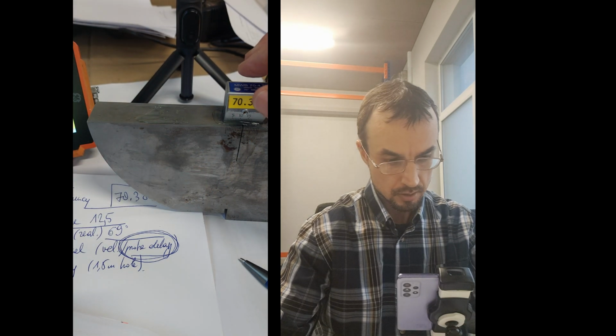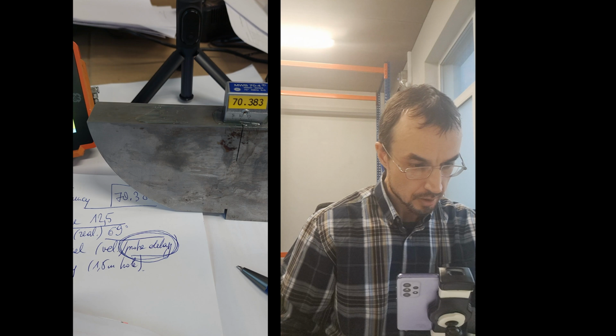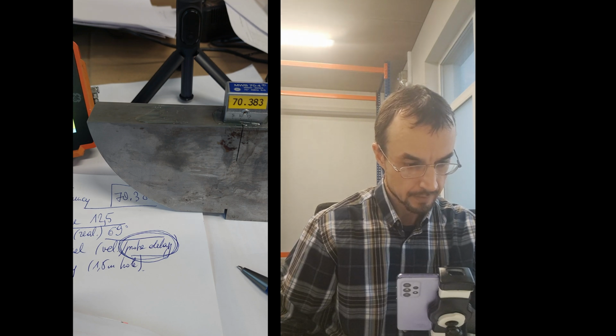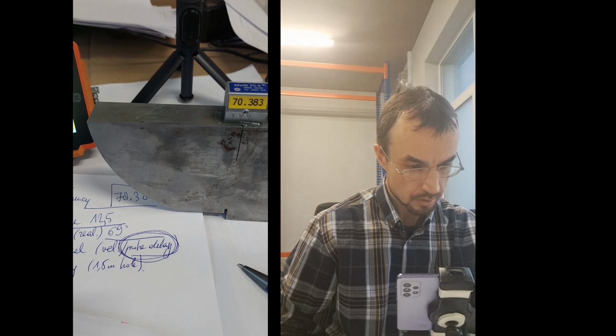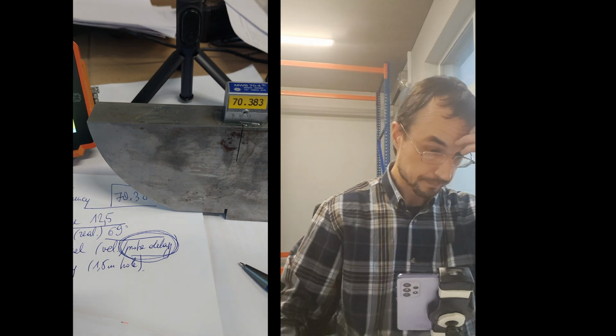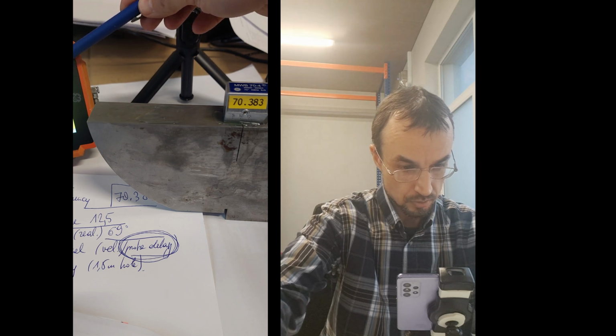Now, let's go to AutoCal. Here. Start of the gate, ref 100. Record off. Now probe angle, thickness, X value. Okay, everything is fine here. What I will be doing now is this thing should be 100. So it will change the probe delay to the...